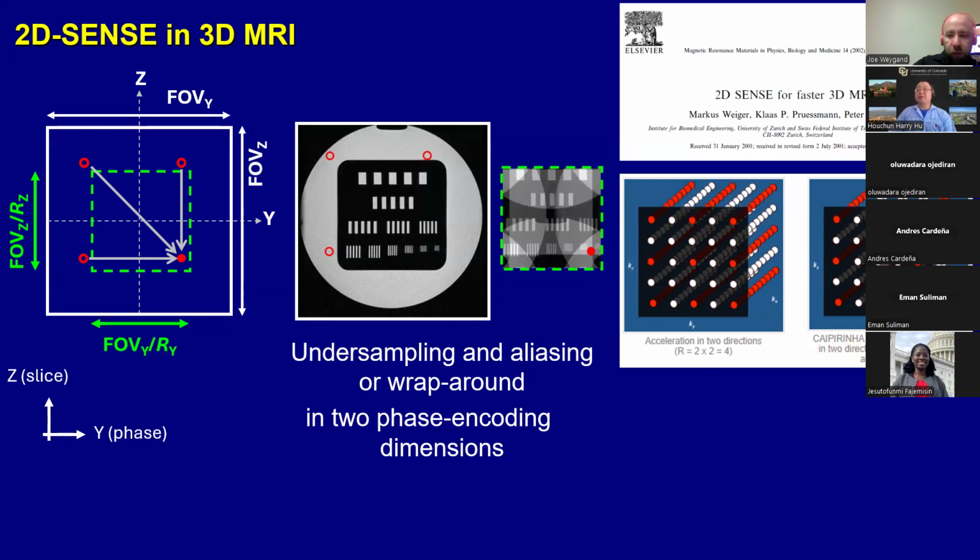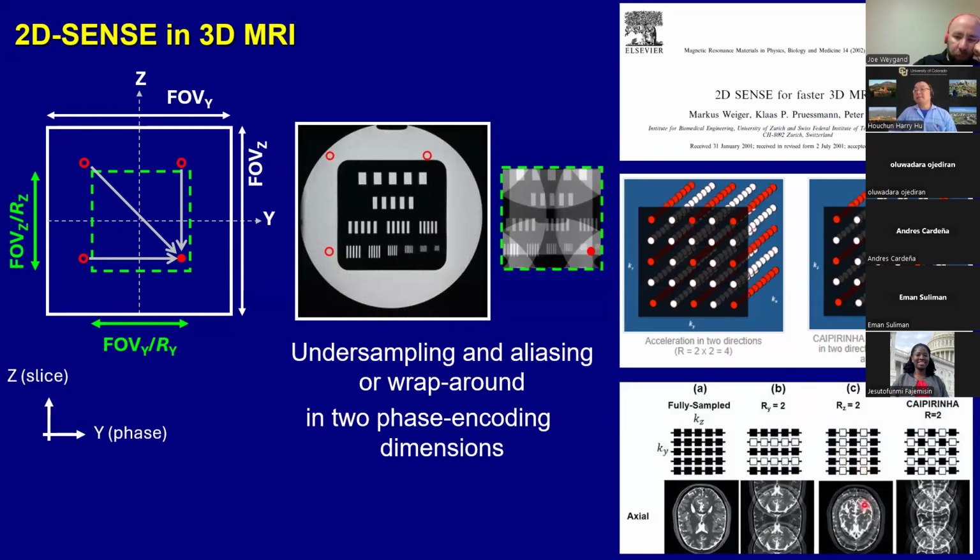The advantage of this, as you'll see in the image below, is that rather than superpositioning a particular slice on top of another slice with conventional skipping, by shifting, you move the other slice that's aliasing to the outside of the field of view. So the acceleration is the same, but the number of pixels that are aliasing is fewer. There are fewer, if you will, pixels for you to unalias or solve. Again, this is not too critical, but just realize that some of this is happening in the background depending on what parallel imaging technique you picked.